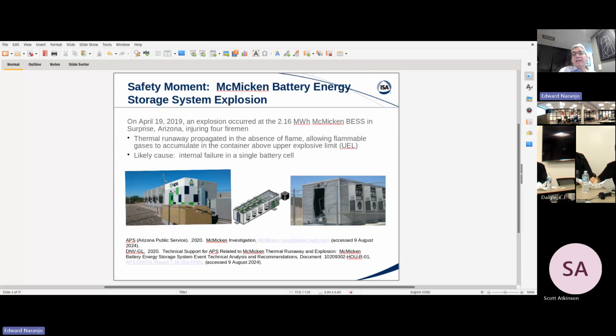Upon opening the door, air went into the container, reducing the gas concentration to the point where it could sustain an explosion, and an explosion did in fact occur, injuring four of those emergency personnel. The likely cause of the incident was an internal failure of a single battery cell.